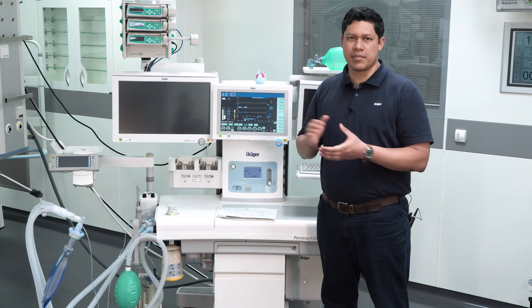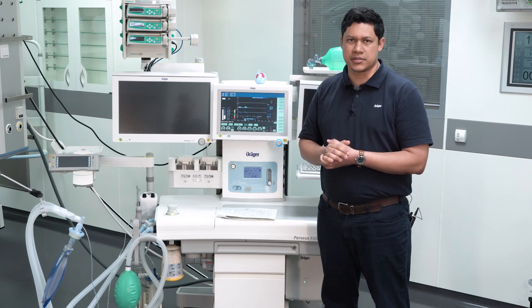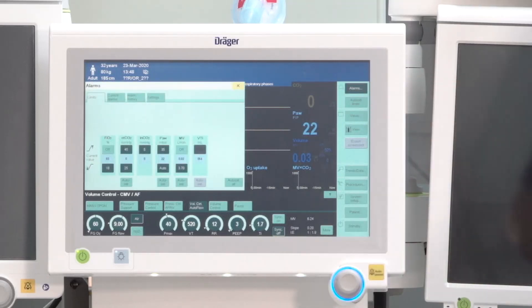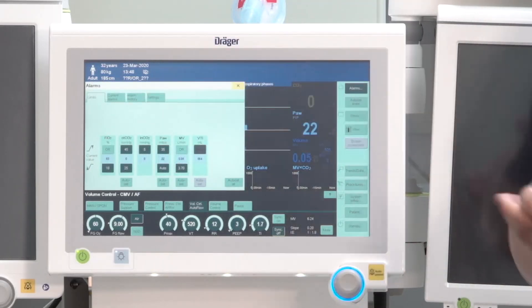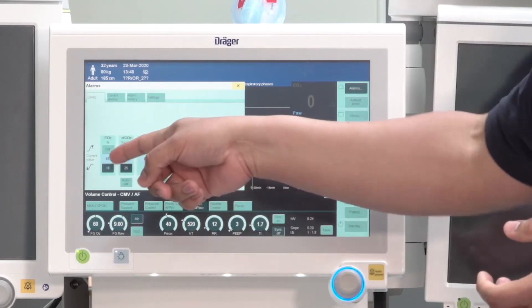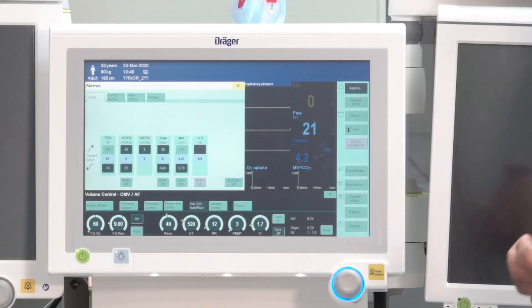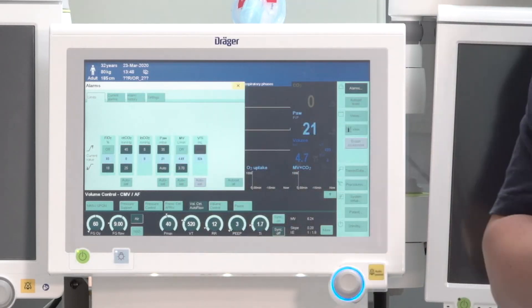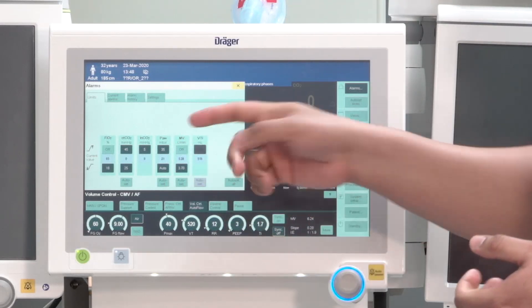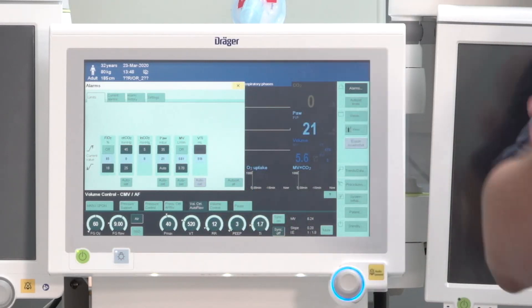Set the alarm limits individually for each patient. To do so, go to the alarm button and you will have direct access to the limits. The most important settings are for FiO2 the low level, for ETCO2 the low and maximum level, for inspired CO2 the maximum level, and for minute volume the low and maximum level.